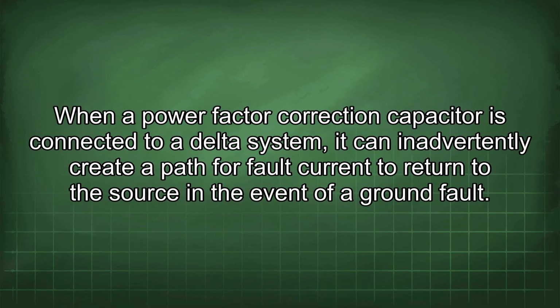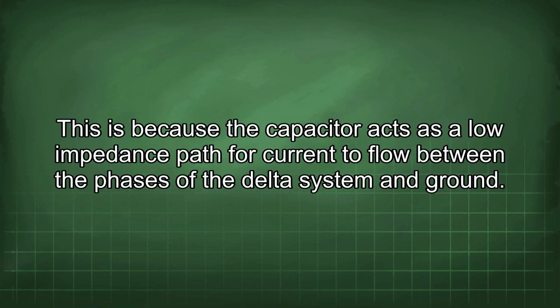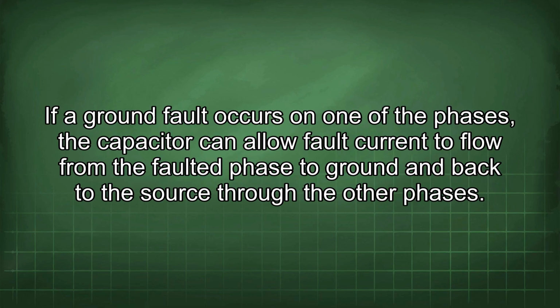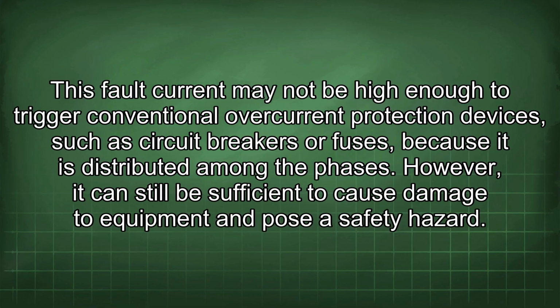When a power factor correction capacitor is connected to a delta system, it can inadvertently create a path for fault current to return to the source in the event of a ground fault. This is because the capacitor acts as a low impedance path for current to flow between the phases of the delta system and ground. If a ground fault occurs on one of the phases, the capacitor can allow fault current to flow from the faulted phase to ground and back to the source through the other phases. This fault current may not be high enough to trigger conventional overcurrent protection devices such as circuit breakers or fuses because it is distributed among the phases. However, it can still be sufficient to cause damage to equipment and pose a safety hazard.